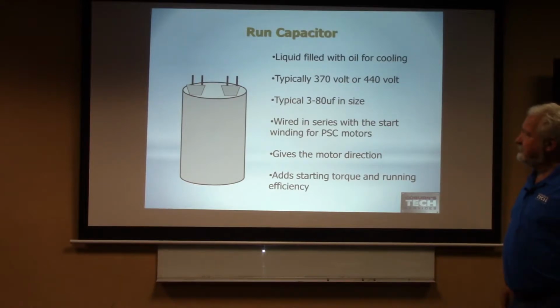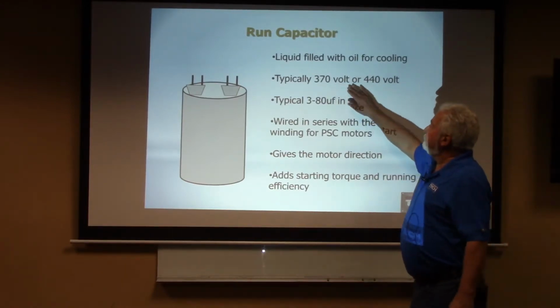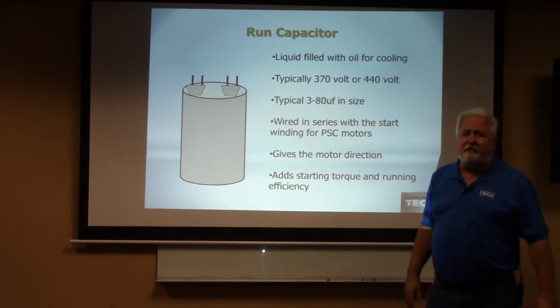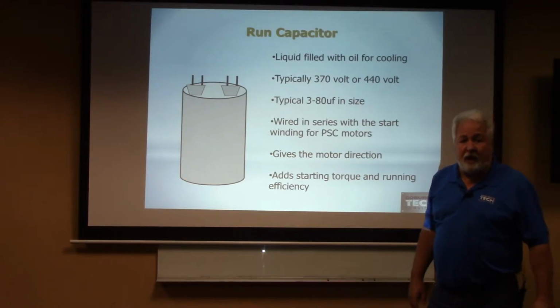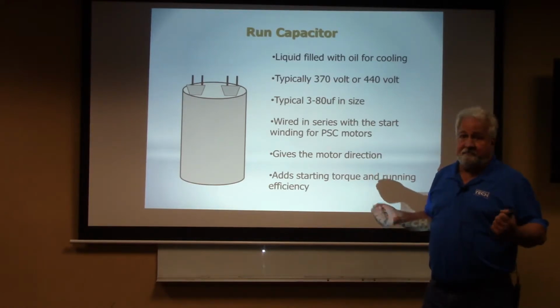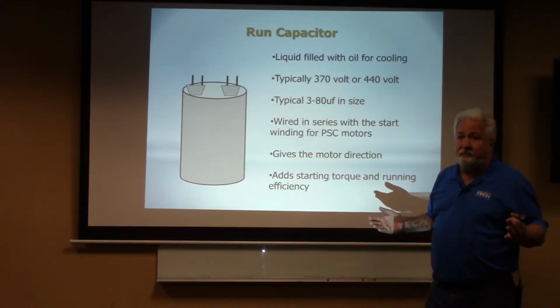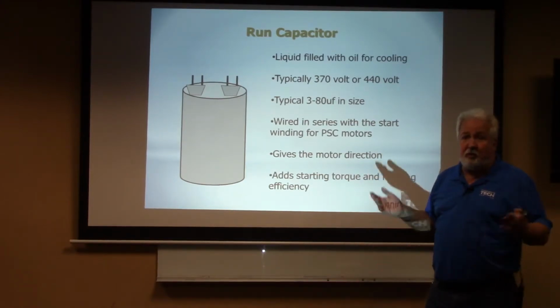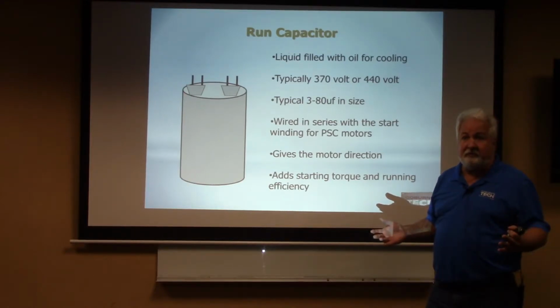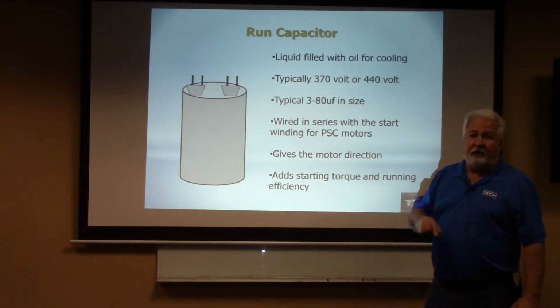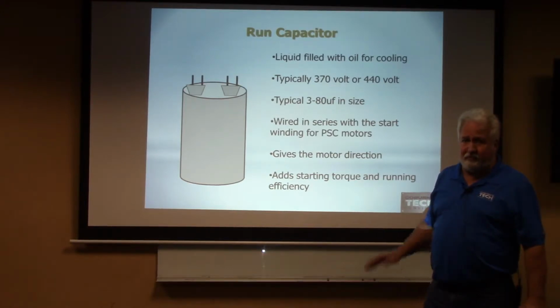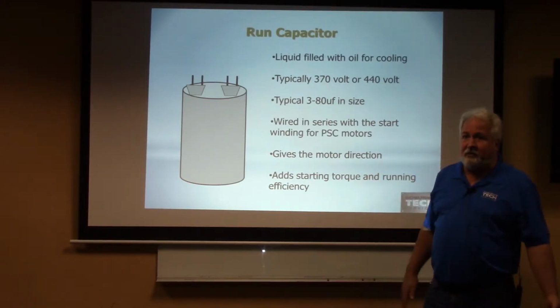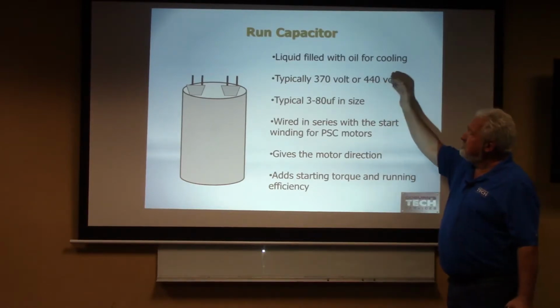Is that right? Absolutely. Typically, they're 370 volts or 440 volts. That is the voltage storage capability of that capacitor. It can hold up to 370, or it can hold up to 440 volts. If you had a choice, put in the 440, because now it can store up to 440 volts. Is that right? I couldn't step down and say, okay, well, I only needed to store 373 volts, so I'm going to go with a 370. It's not going to be large enough, okay? You can always go up.